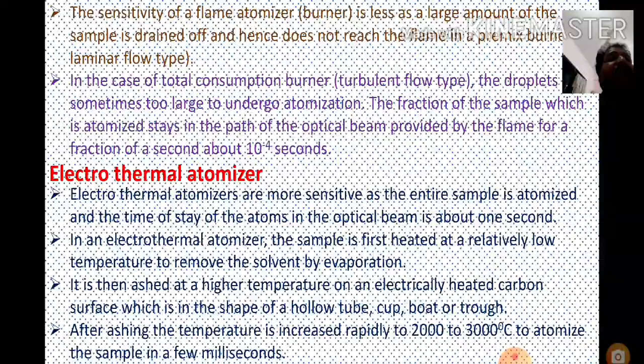An electrothermal atomizer consists of a graphite tube open at both ends. This tube is about 5 cm long and has an internal diameter of about 1 cm. The sample is introduced through a central window in the tube. Two electrodes are fitted at the ends of the tube. A stream of an inert gas like argon or nitrogen flows in and around the tube to prevent possible oxidation of the graphite material. The entire assembly is kept in a water-cooled metal jacket. An electrothermal atomizer is popularly referred to as a graphite furnace.